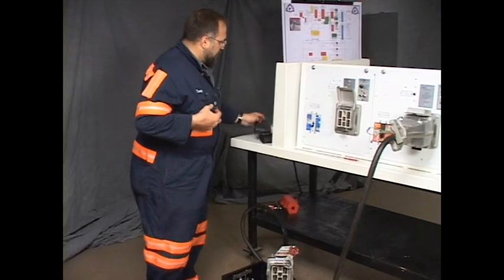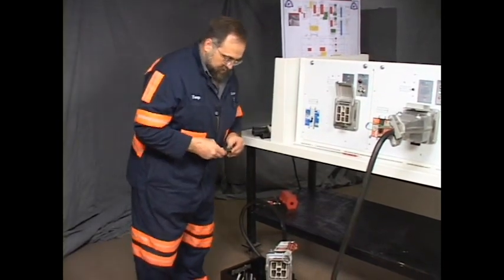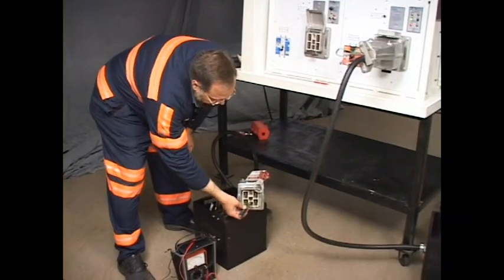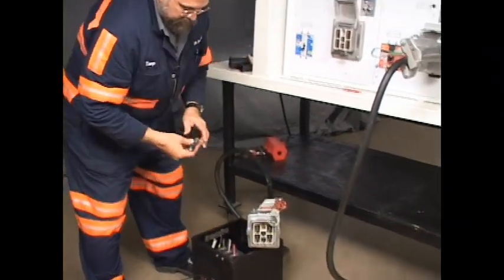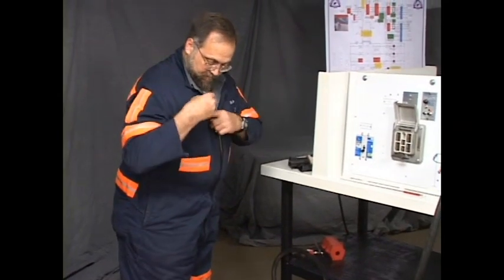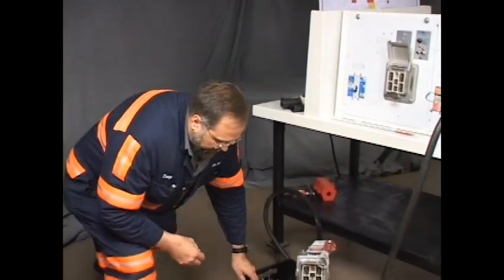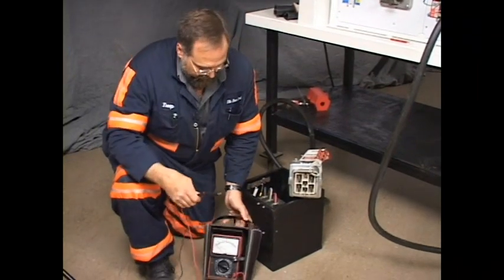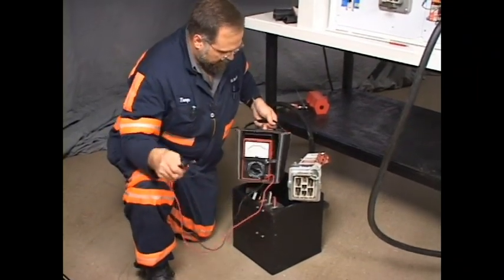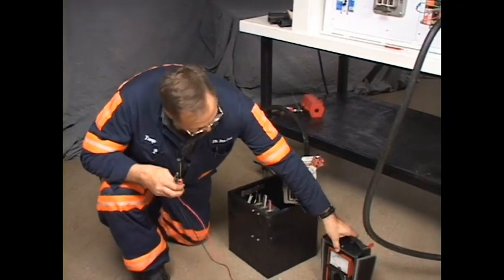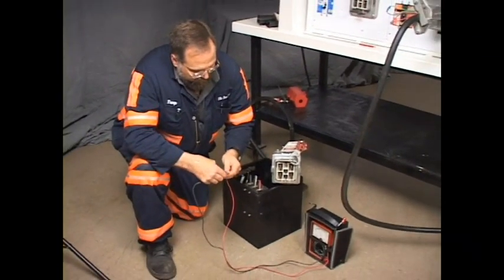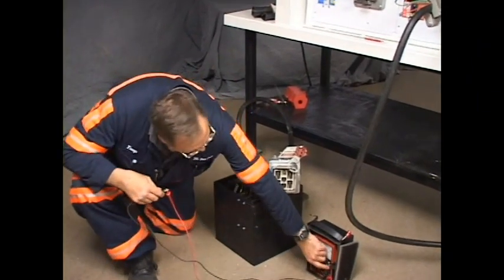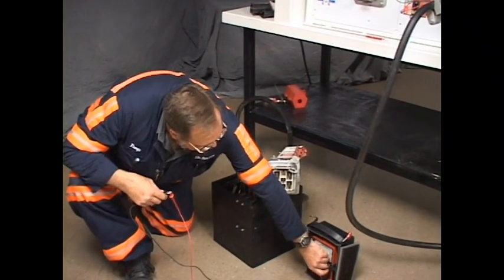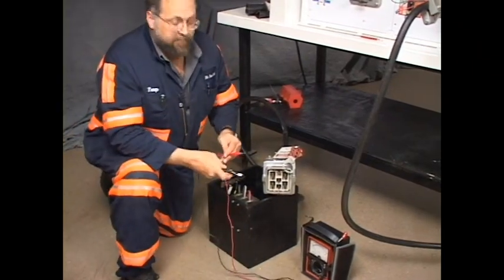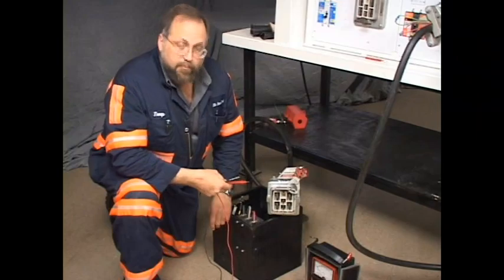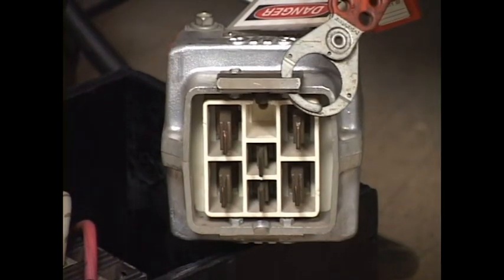Now, this is de-energized. It's unplugged. We're still going to make a voltage test. This is not the only cable on this section. There's no voltage. Now it's safe to handle. Take the meter, zero the instrument. I'm going to read continuity from the ground conductor to the monitor on the end of our coupler.